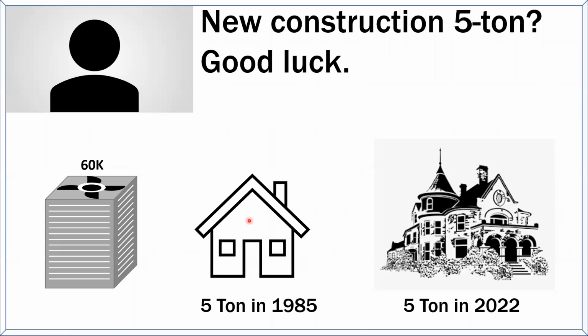Jack used to go around the country before any of this, we're talking 20 years ago. I took my first class from him. He was saying 5-ton systems don't work, right? Why don't they work? Because you've got to get that air to go 2 or 3 times as far, through twice as many fittings, with velocities twice as high as in a 2.5-ton system.